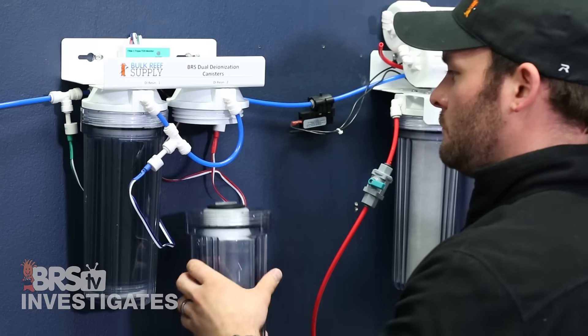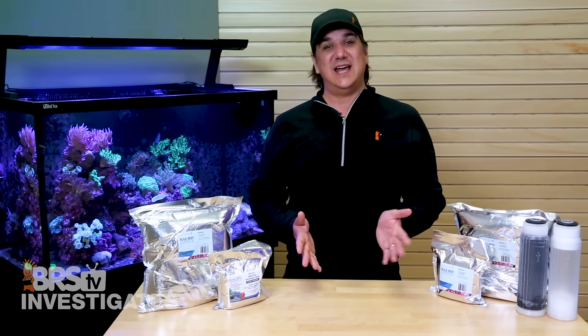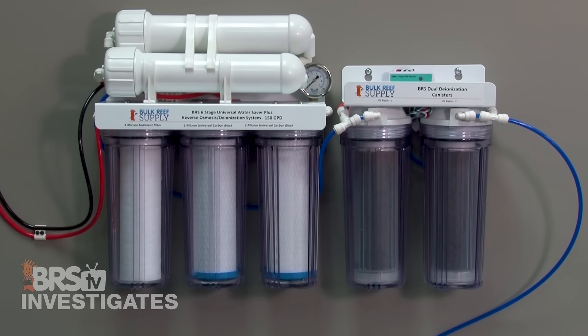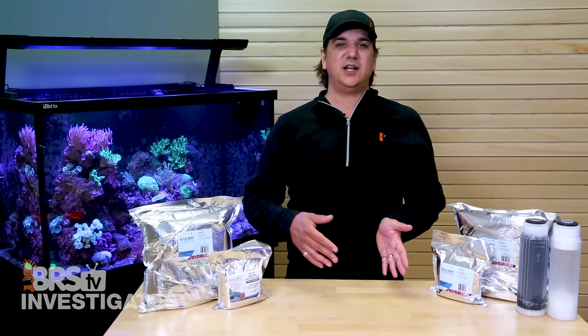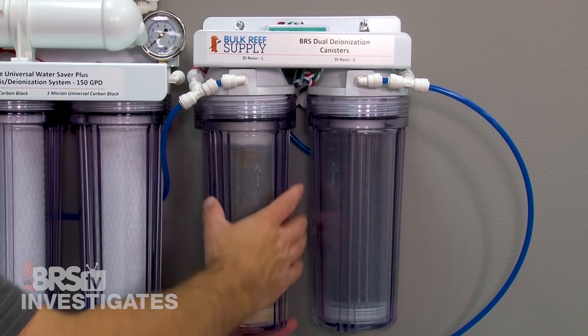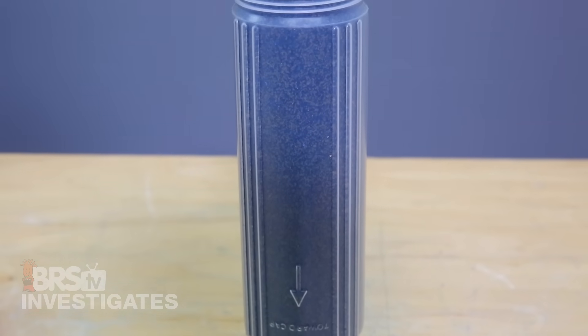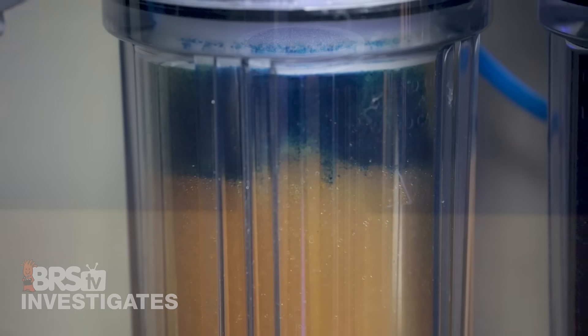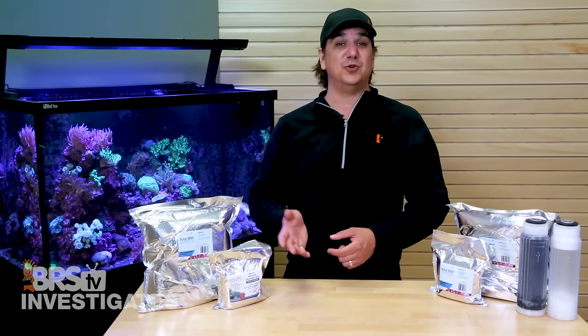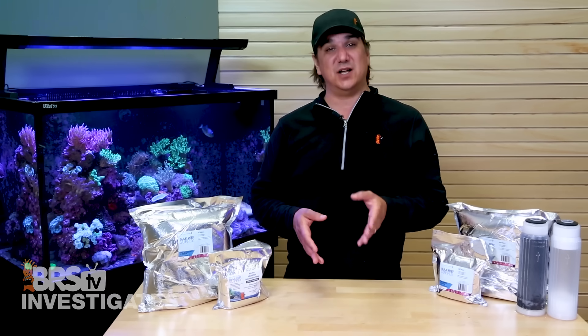I have two alternative options which are both simpler, have clear indications of depletion, work on a wider array of contaminants, and are lower cost as well. The first is a simple two-stage DI. Like most filters, DI cartridge performance increases with contact time — the longer the contact time, the better the performance. With a dual-stage DI you run the first canister to depletion and when it's exhausted, replace it with a new one. The benefit is that with a single DI you start with a full 10 inches of fully charged resin, but towards the end you may only have an inch or two of fully charged resin, and performance on the hardest-to-remove elements will decrease — especially because there is a higher concentration of the weakest-bond elements at the top.